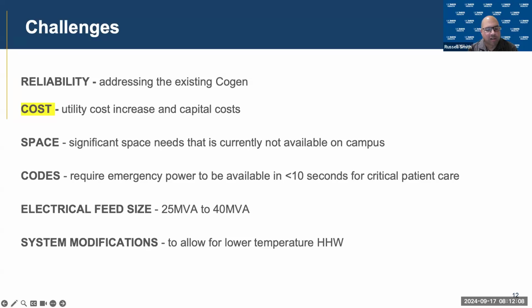Electrical feed size: we're working on getting the first 40 MVA connection in order to get some added resiliency and redundancy to the utility. We have to upsize our existing 25 MVA to 40 MVA. And then one of the final challenges is the heating hot water. This is throughout all the existing buildings - piping sizes, piping that's not rated for the lower temperatures, as well as heating coils and those types of things that all have to be studied and then retrofitted to work with the lower temperature.